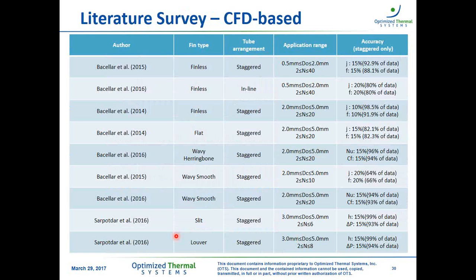design space. And recently, the University of Maryland and OTS have joined efforts, and we now have 9 new correlations for various tubes and fins, focusing on diameters below 5 millimeters. They are CFD-based correlations. So we use CFD to gather the source data, and then we have a correlation that can accurately predict the CFD simulations. And though they are not empirical, they are a very inexpensive way of predicting performance. So it gives us the freedom of not having to rely on CFD or measurements to assess the performance of tube fin heat exchangers, and gives us some more power in terms of design.